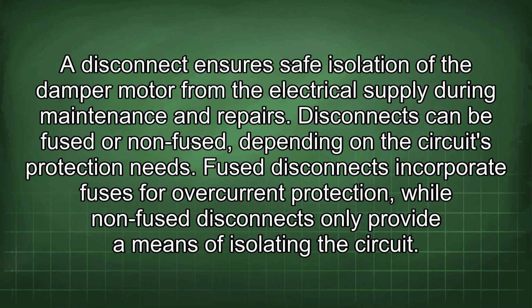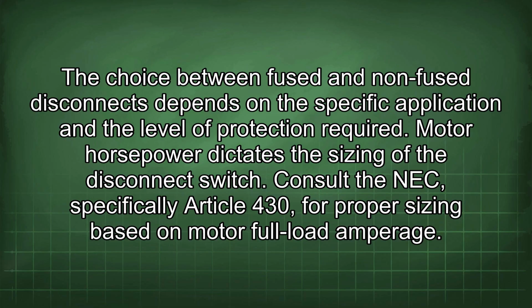A disconnect ensures safe isolation of the damper motor from the electrical supply during maintenance and repairs. Disconnects can be fused or non-fused depending on the circuit's protection needs. Fused disconnects incorporate fuses for overcurrent protection, while non-fused disconnects only provide a means of isolating the circuit. The choice between fused and non-fused disconnects depends on the specific application and the level of protection required.